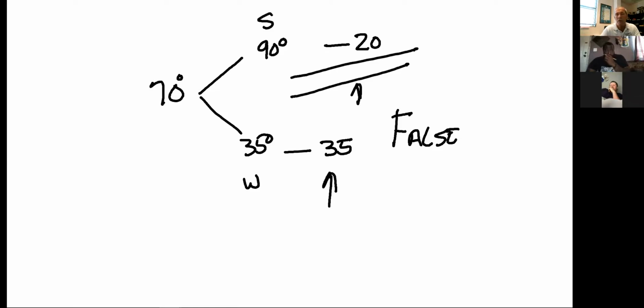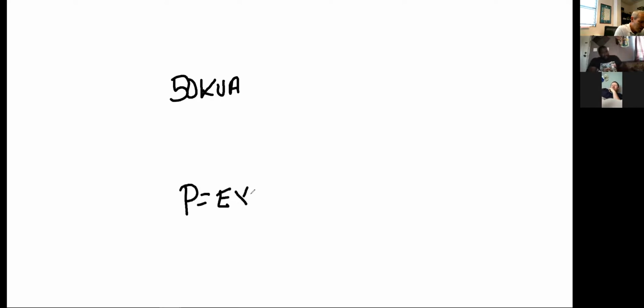Let me clear the screen and we'll use this as an example. I like using a 50 kVA because it's a good round number, and this is why we're doing this in essence. I've got a 50 kVA, and through my amperage, we know that P equals E times I. So I'm going to do 240 volts, and I've taken an amperage reading of 460 amps. Figure P for me right here.